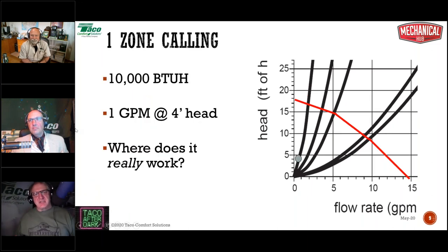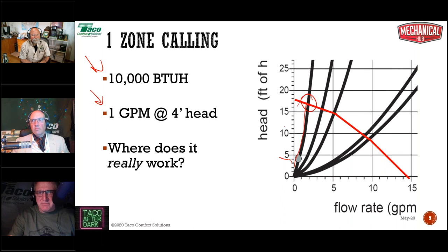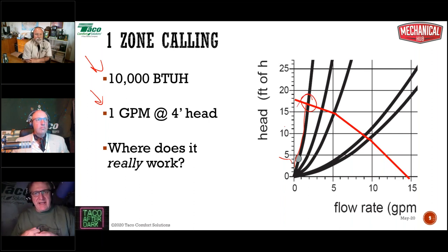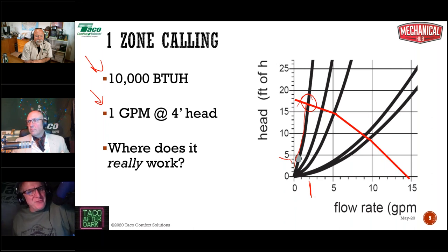Let's also take a look at the smallest zone. Our smallest zone, let's say it's 10,000 BTUs. Well, using the formula, that tells us it's going to be 1 gallon a minute. And let's say that 1 gallon a minute zone happens to be 4 feet of head. So it needs to be right here. Now, where's it going to really work? Well, it's going to really work where the system curve intersects the pump curve. So it's going to be working way up there at about 17 feet of head and at about 2 gallons a minute instead of the one that's required. So I'm doubling up on my flow rate to deliver those 10,000 BTUs.